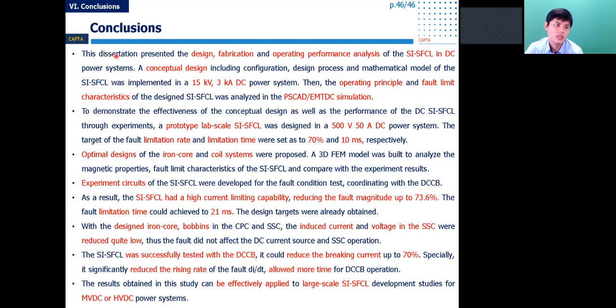Finally, the conclusion. This dissertation presented the design, fabrication, and operating performance analysis of the SFCL in the DC power system. A conceptual design including the configuration, design process, and mathematical model of the SFCL was implemented in a 15 kilovolt, 3 kiloampere DC power system. Then the operating principle and the fault limiting characteristics of the designed SFCL were analyzed in the PSCAD/EMTDC simulation.